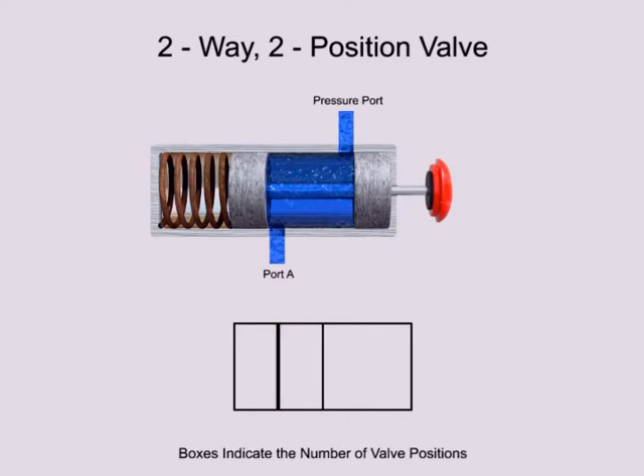For complex valves, the ports may also be labeled. The input port is typically labeled P for pressure. Outlet ports are typically given alpha characters starting with A. Other times, the letter stands for the destination of the fluid — for instance, the letter T would indicate a port connected to a tank. This is a fairly simple valve, so port labels are not required.